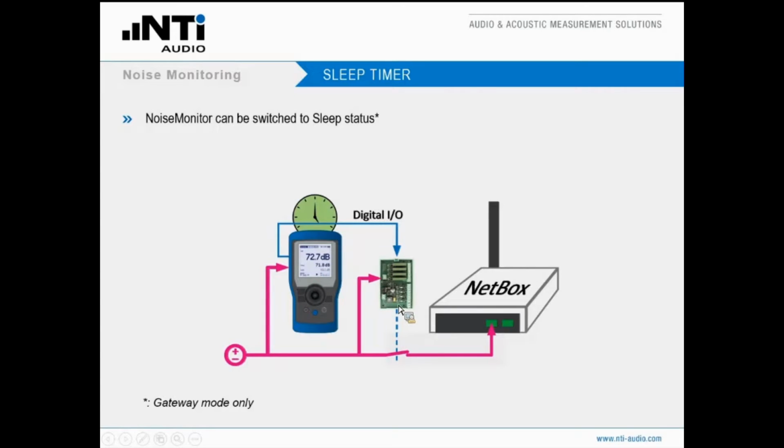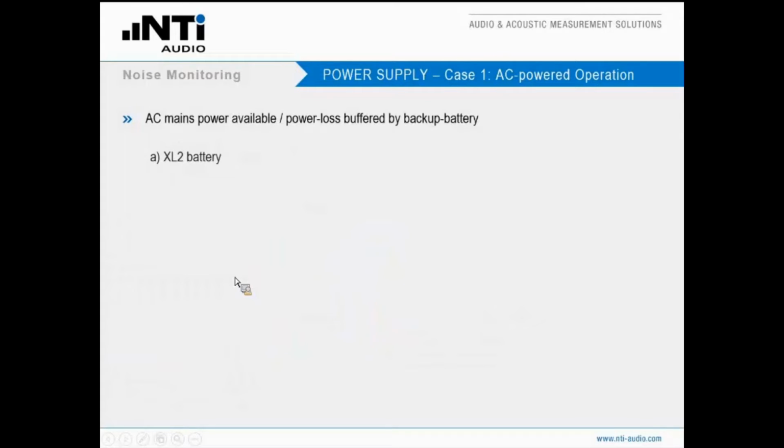And as soon as the time has elapsed and the wake-up time has come, the XL2 switches itself on again, as well as, through that PCB, the netbox, and you are online again, and the whole noise monitor is working as required. Keep in mind that this feature is only available in gateway mode. So we have minimized power consumption, and the master of this whole procedure is the XL2.